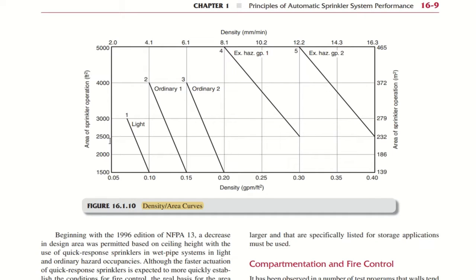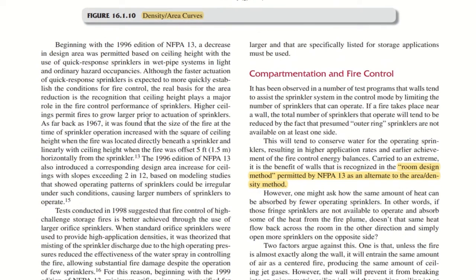And for extra hazard group 1 occupancies, you have 0.3 GPM per square foot, and the sprinkler area of operation, or the design area, or the hydraulically calculated area, shall be 2500 square feet. For extra hazard group 2 occupancies the area is the same, but the density will be 0.4 GPM per square foot. This is a very important topic. You need to understand this graph. In future sessions we shall discuss the hazard occupancies. You can also find the classifications of hazards in my other course on NFPA 13, where you will get all the details about these occupancy classifications.